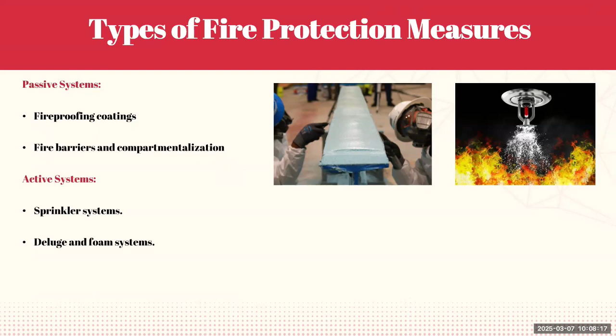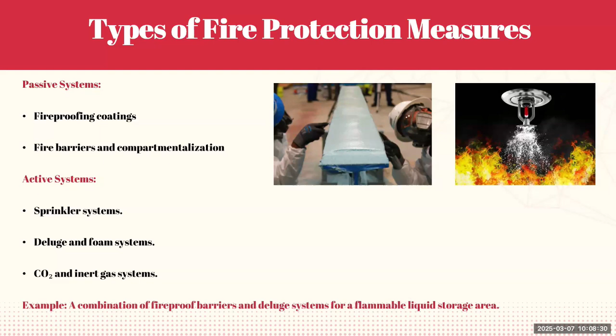So we need to ensure that we have fire barriers and proper compartmentalization. As for active systems, these include sprinkler systems, deluge and foam systems, and also CO2 and inert gas systems. An example would be a combination of fireproof barriers and deluge systems for a flammable liquid storage area, so we have both a passive system and an active system in place.